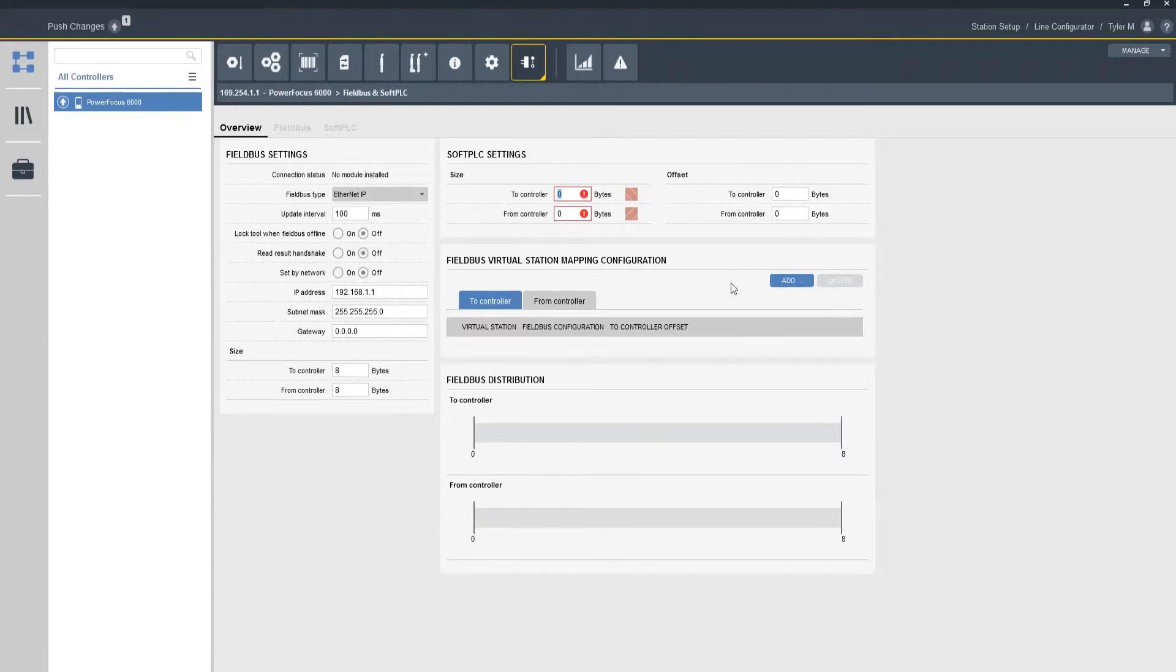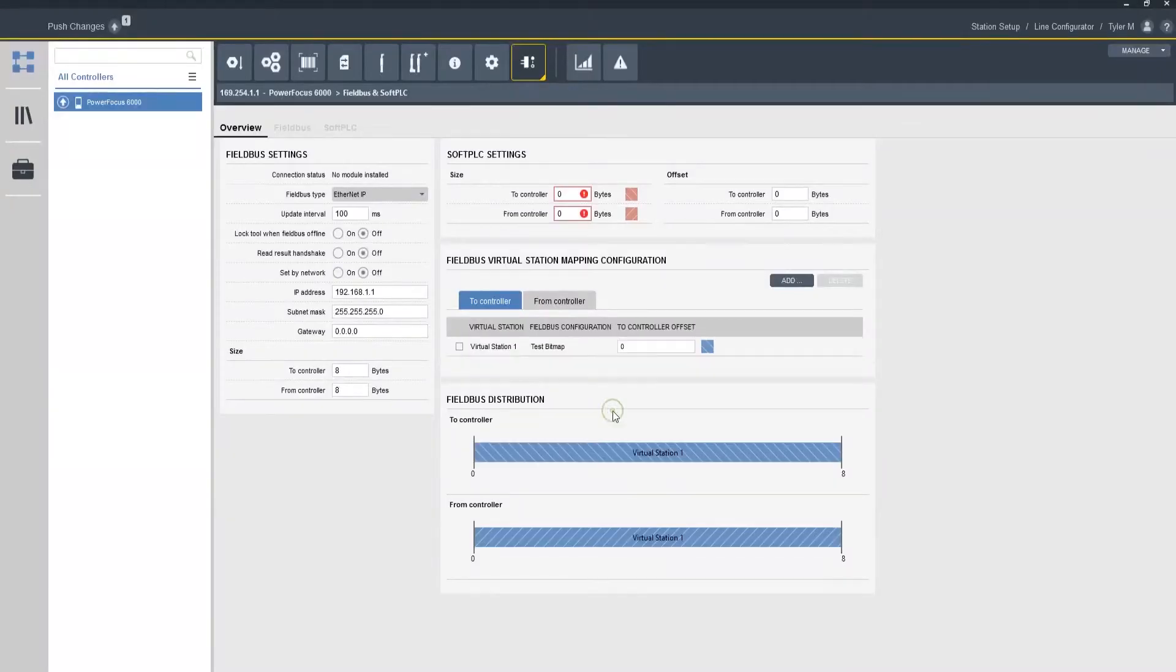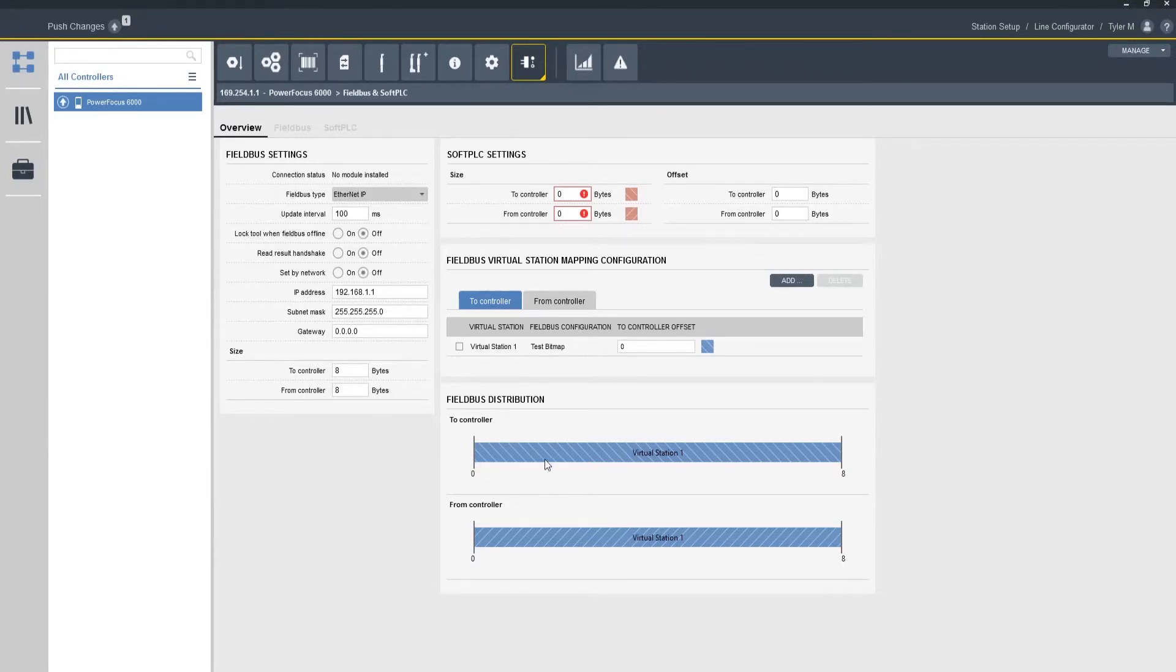So we're actually going to have the settings for our generic field bus virtual station mapping configuration. So I'm going to come over here I'm going to click add. So here we have a drop down. So if we do have multiple tools or multiple virtual stations on this controller we have the ability to set a separate bitmap for each tool. So I'm going to select the only virtual station that I have programmed, virtual station one, and then I'm going to select my configuration. It's the test bitmap which we just created. Now I'm going to click that, click on add, and now you're going to see that I have a very clear breakdown of which virtual station is going to be using which portion of the bitmap.